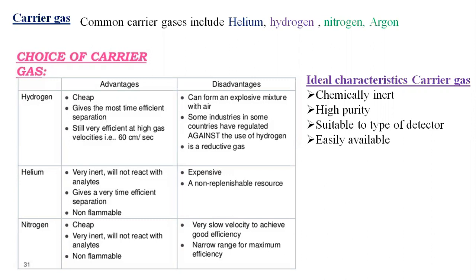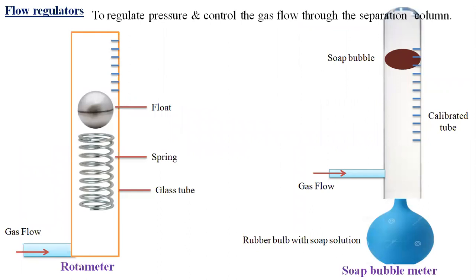The ideal characteristics of a carrier gas are: chemically inert, high purity and easily available, and suitable to the type of detector. Next are the flow regulators. When the carrier gas is stored in the cylinder at high pressure, it travels with some flow. To regulate or maintain a constant flow, we use flow regulators to regulate the pressure and control the gas flow through the separation column.